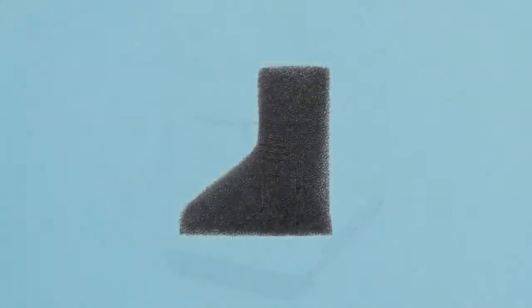The grey carbon inlet filter is for filtering large particles and must always be in place when treatment is running. It is recommended that the filter be replaced every 12 months and that it is checked and washed at least once a week. Please reference the user or clinical manual for cleaning instructions.